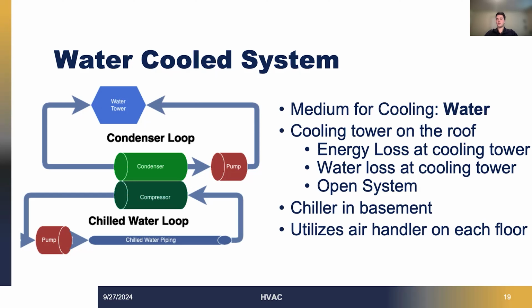These systems are typically used in large office buildings, hospitals, and schools, where efficient cooling is essential for maintaining a comfortable environment. So as you can see in the image above, those two loops, the secondary and tertiary water loops, are the condenser loop as shown at the top, which has a water tower on the roof of the building, and the chilled water loop is shown in the bottom, which is used to chill the water for the air handlers.